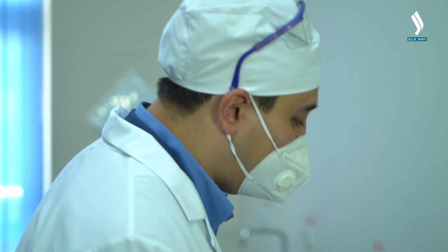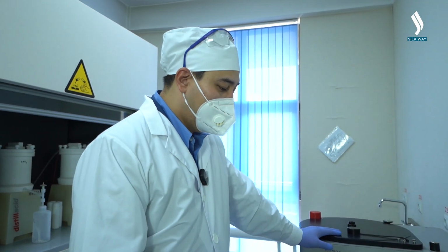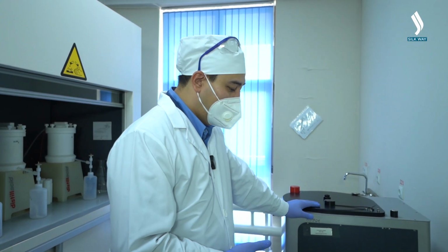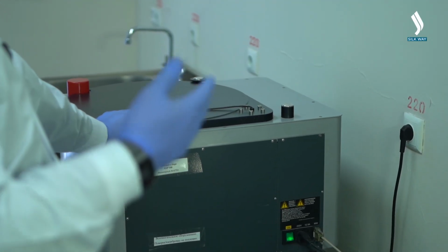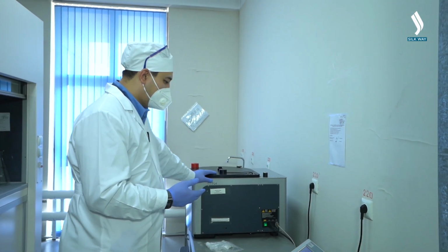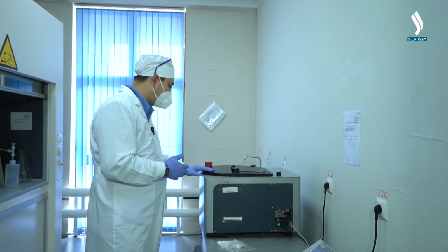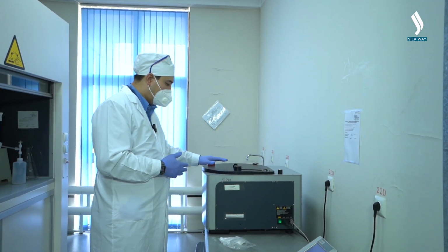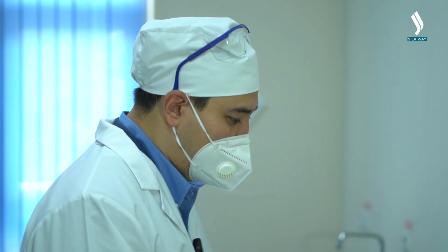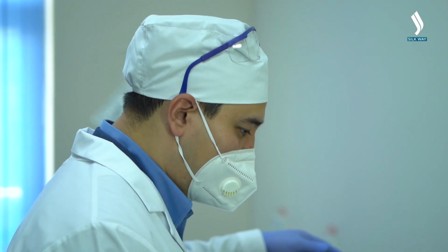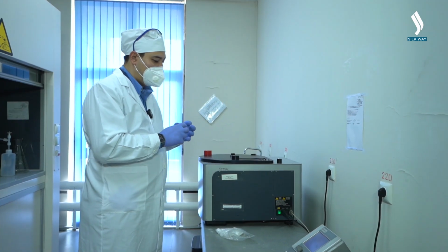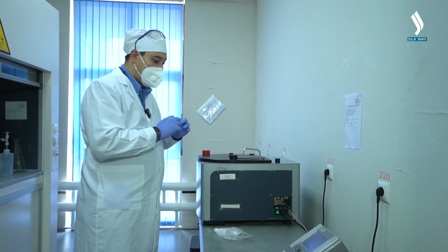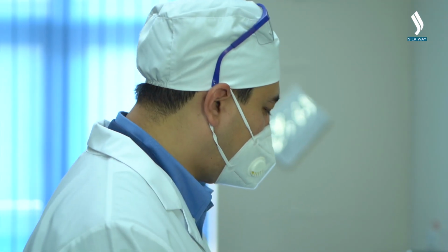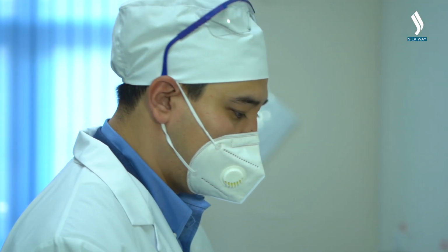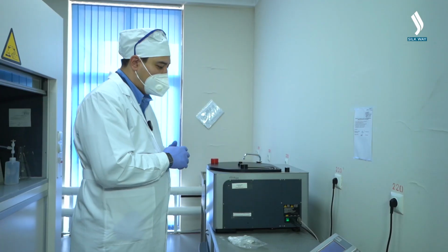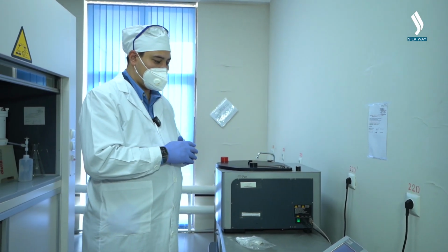Now this machine will make the probe liquid. It will dissolve the ore using the acids that I added before. The machine uses microwave heating and a circling system, so the probe will dissolve equally. The process will take 1 hour and 40 minutes. The temperature is 180 degrees Celsius.